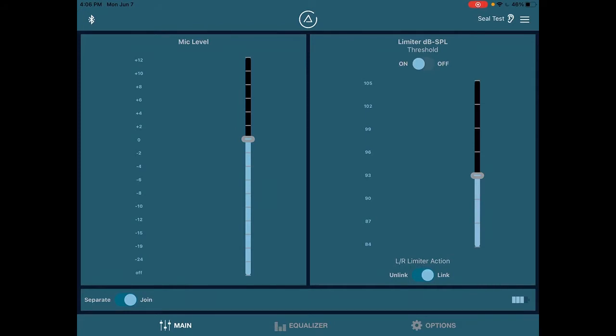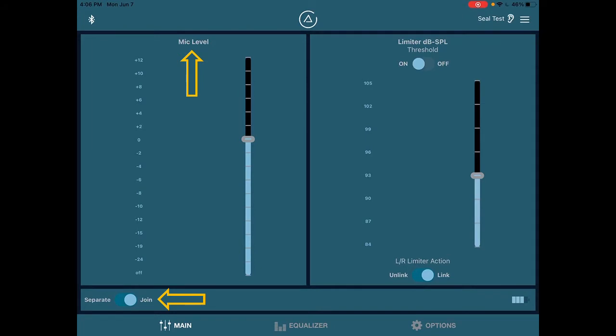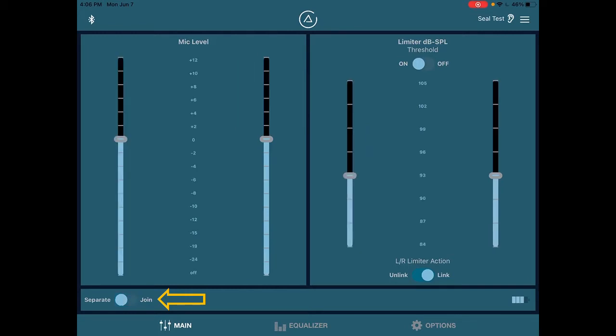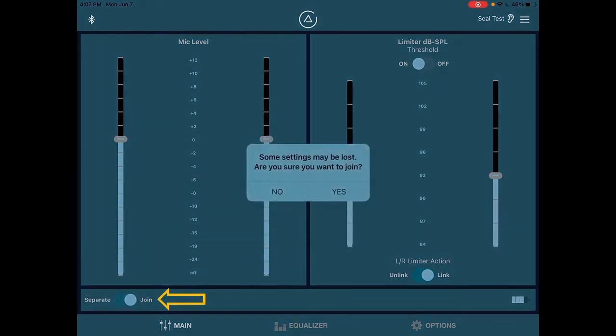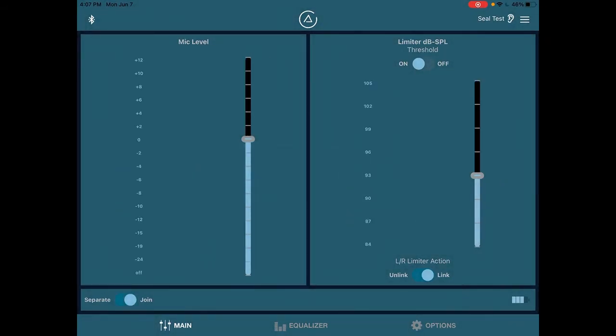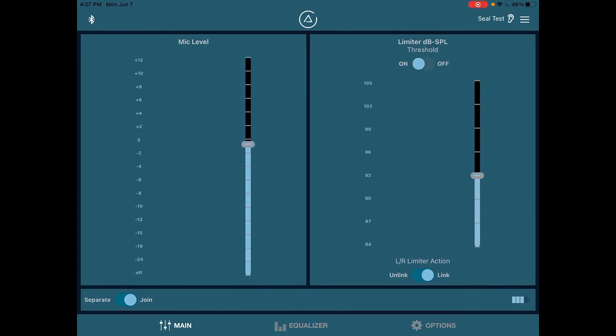Now on this page, we have mic level and we have limiter. The mic level right now is set to join. That means the ears are going to be adjusted together. And that's the way that most people will use this system. For individuals who might have different preferences for listening or perhaps have different hearing statuses between their ears, they might want to have the ears separate. And then things can be adjusted right ear or left ear. For the purposes of this demo, I'm going to join them. The plus signs to the left of the numbers will increase the volume or intensity of the mics or gain. You can also decrease. Or you can leave it at zero.